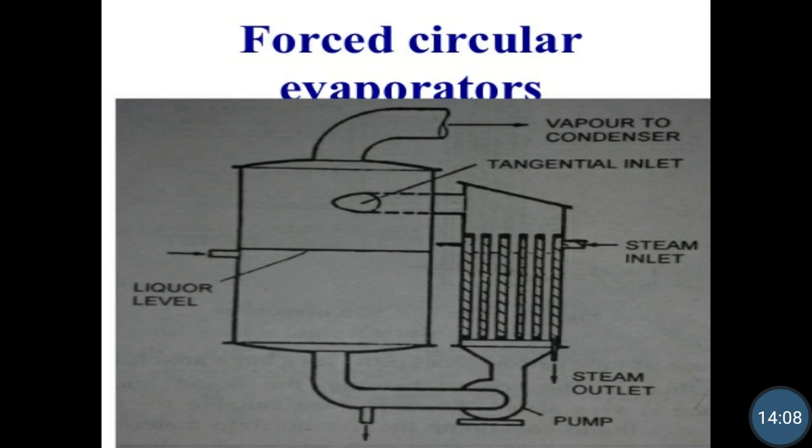It has some advantages, like there is a rapid liquid movement which improves the heat transfer. Because of the agitation, the transfer of heat is increased, and the evaporator is useful for the evaporation of viscous liquids or material that deposits solids readily. Generally, for viscous liquids which deposit on the walls of the evaporators, forced circulation evaporators are useful.